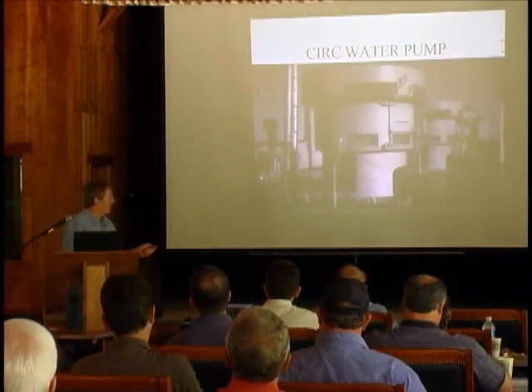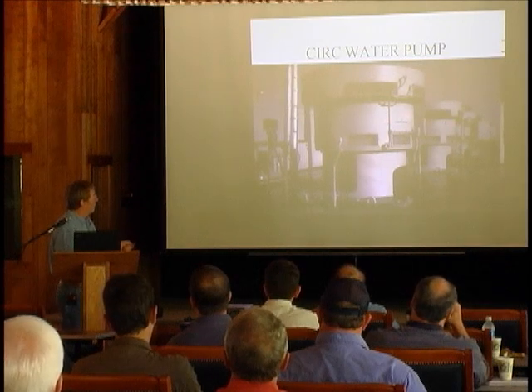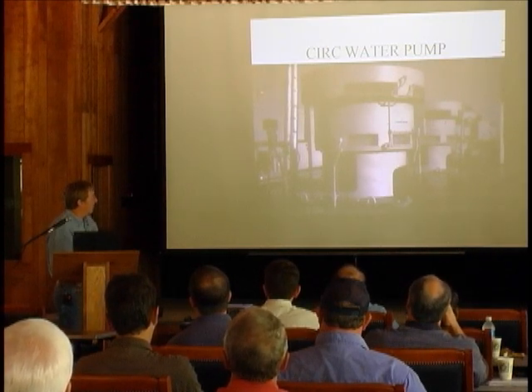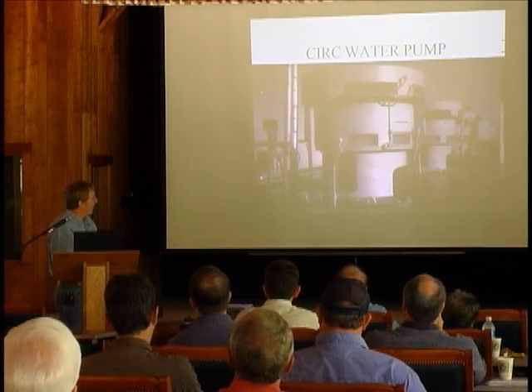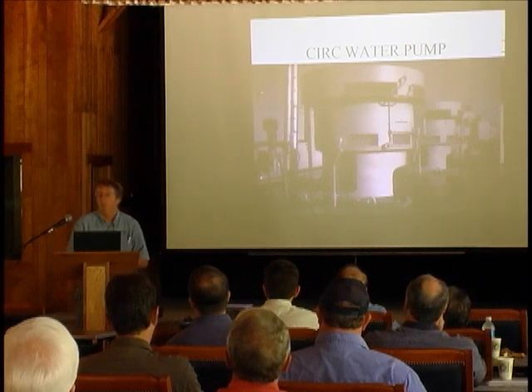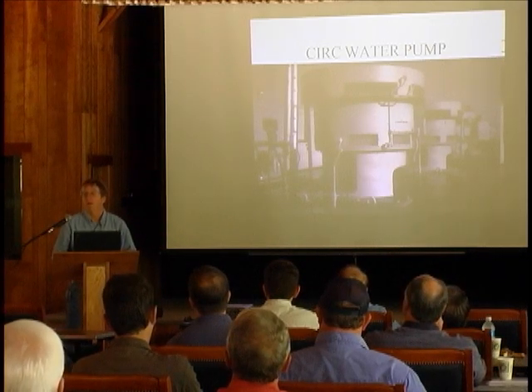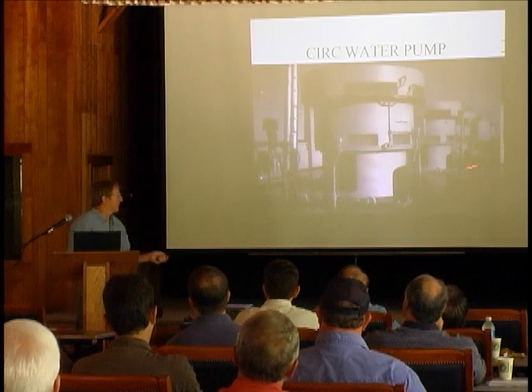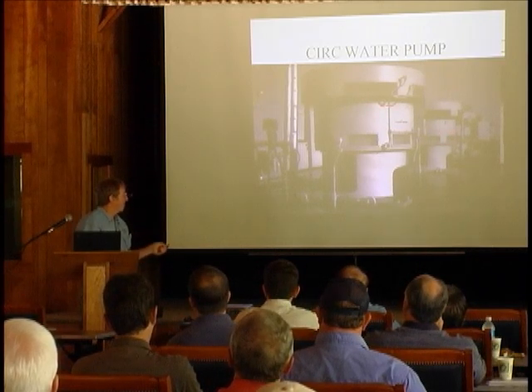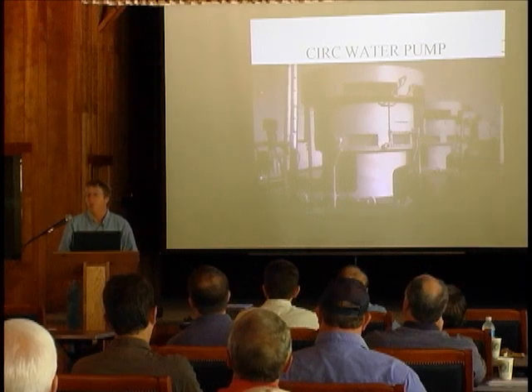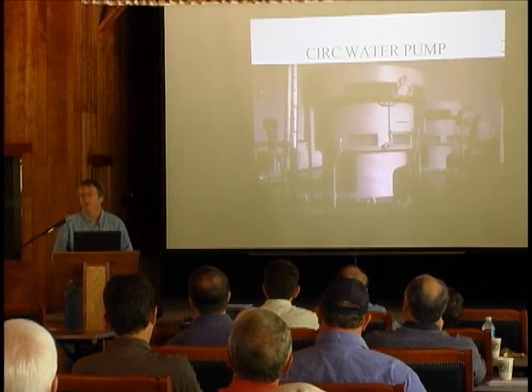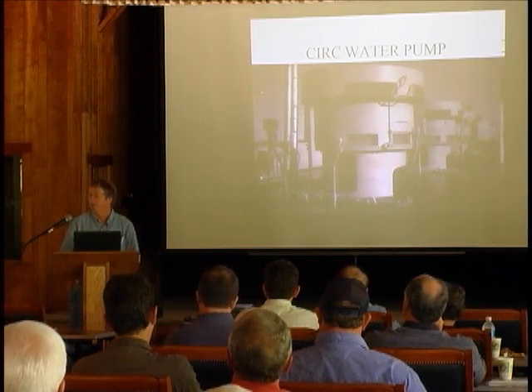So you note right here, there's 3 pumps here, and this is on a lake. In the wintertime, the water gets quite cool in this lake. So the operator said, well, these things are a couple thousand horsepower, so instead of running 2 out of the 3 pumps, which is normal operation, we'll just shut 1 pump off. We'll save 2,000 horsepower, and we're doing a good thing here.